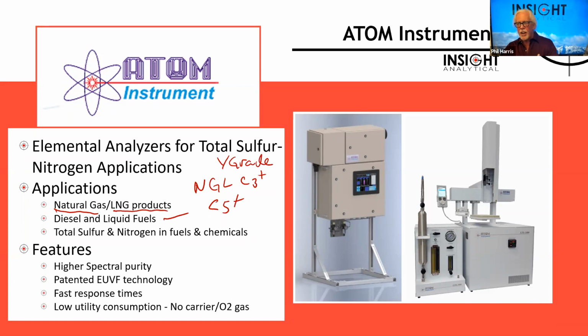Available as both an online device and a laboratory device. Big advantages are this higher spectral purity, eliminates interferences, very fast response time, and low utility consumption. Some of these devices will use oxygen to help promote the conversion of the sulfur to sulfur dioxide. And the ATOM furnace is quite good at being able to do that with just running instrument air. So again, this is for a total sulfur measurement in hydrocarbon type fuels.